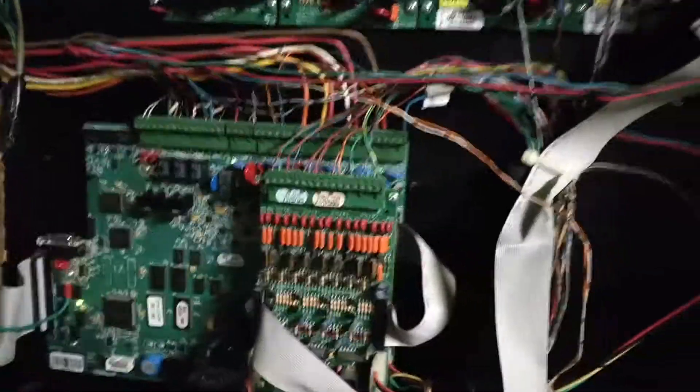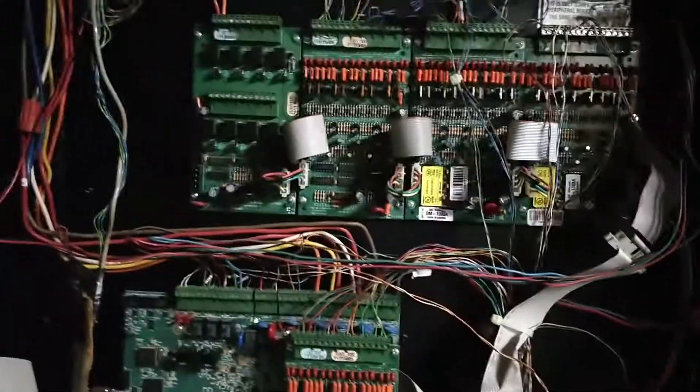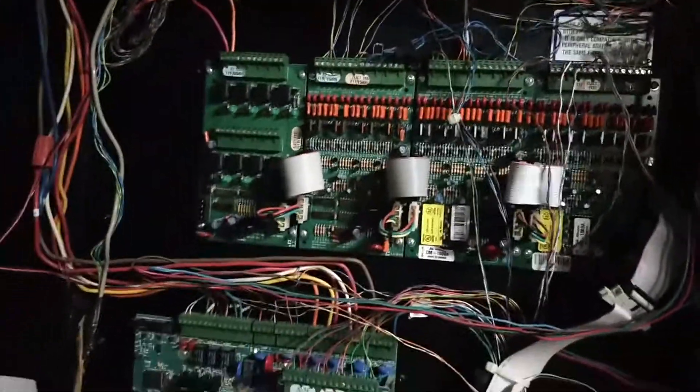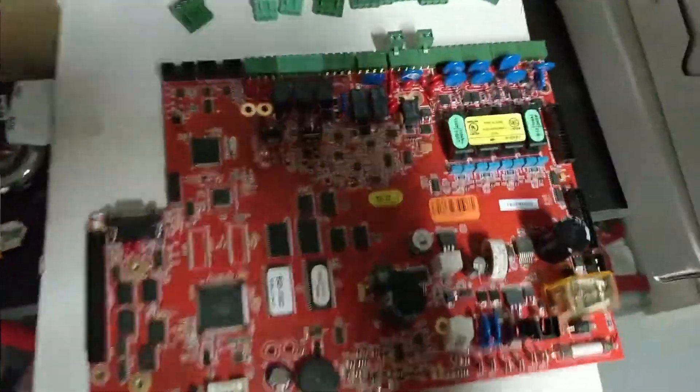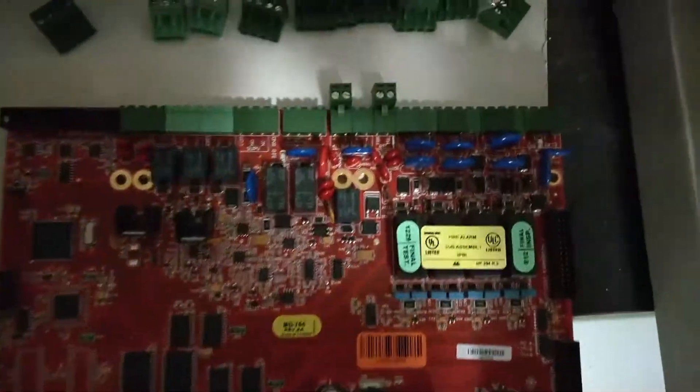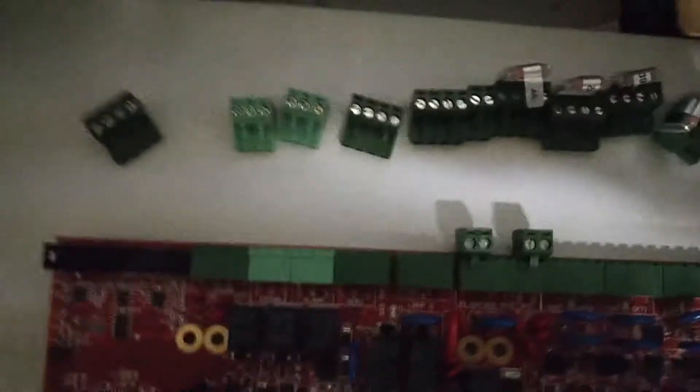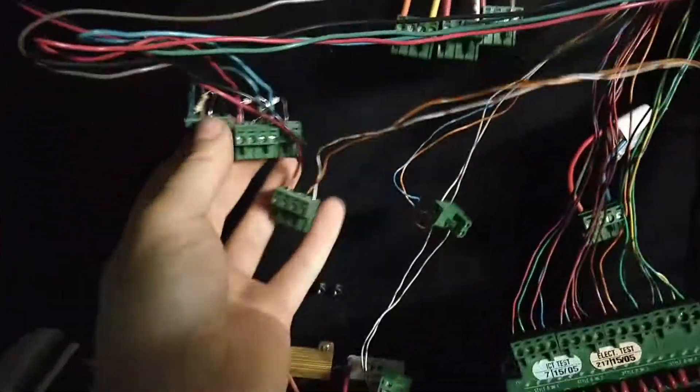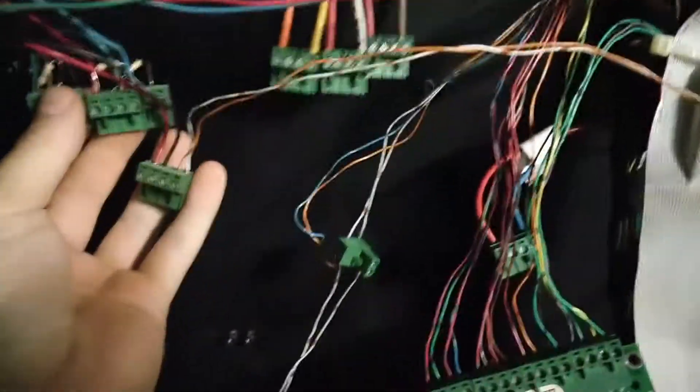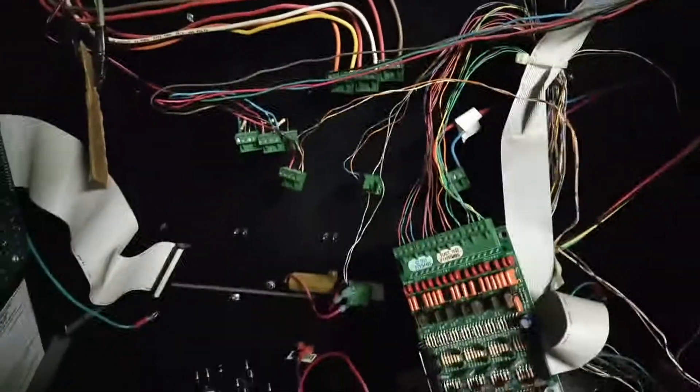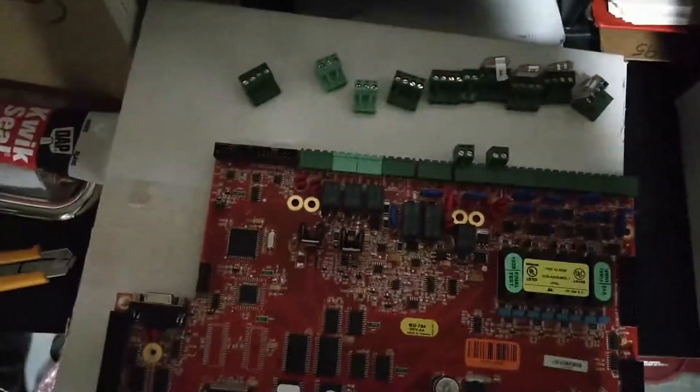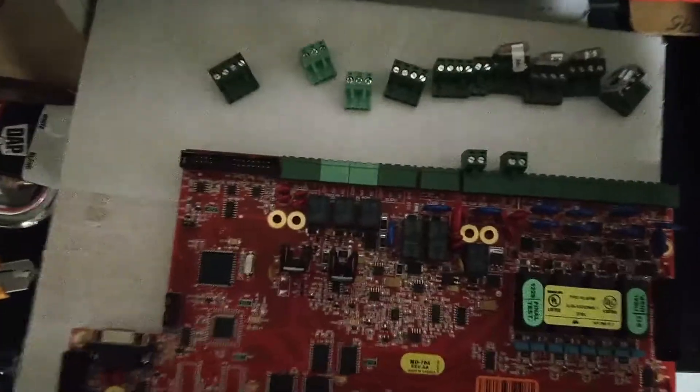It's like 3:30 in the afternoon on a Monday. You can see this panel is a little bit messy too. I might try and clean some of that up, but again I don't want to spend too much time on this. So I'm just going to get started. So one thing I really like about Mircom - here's the new board you can see - not just Mircom but just removable terminal blocks in general. Here's the old one. You can just unplug the terminal blocks and then slide your new board in. Plug everything in. There you go. You're not messing around with undoing all your little terminals and re-plugging wires and maybe having to strip them. It's just a nice thing. I wish all manufacturers did that.